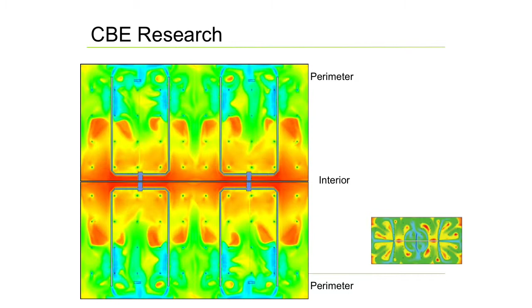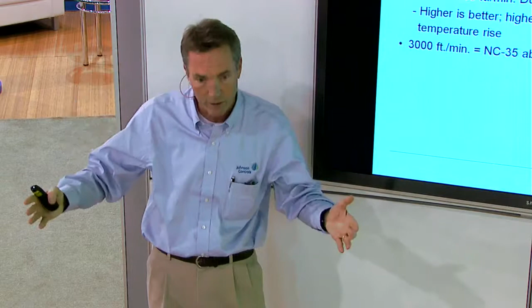One other thing, another new thought in terms of methodology to get that cool air out there, is to increase the velocity of the leaving air at the end of that duct. Traditionally we've thought in terms of maybe 1,200 to 1,500 feet a minute. That's been textbook, and that comes from our overhead friends, thinking if I get above that, I'm going to have noise issues with high pressure static.